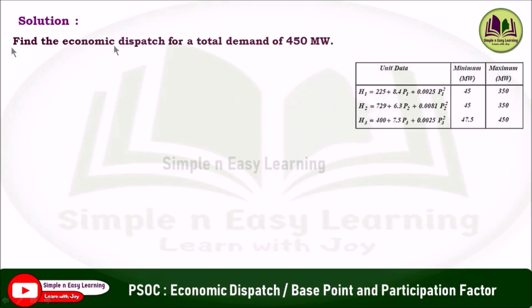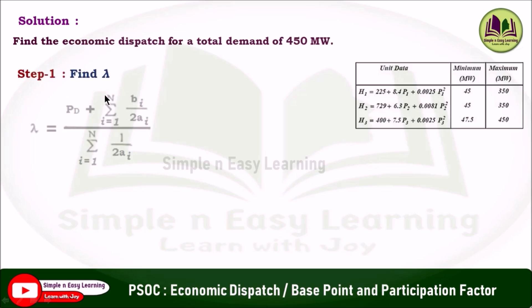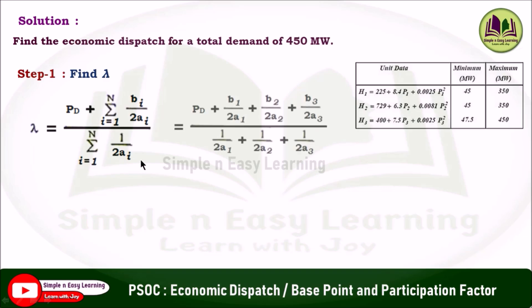Solution — Part 1: Find the economic dispatch for a total demand of 450 megawatt. Step 1: Find lambda using the formula: P_d plus summation (i=1 to n) of b_i / 2a_i, divided by summation (i=1 to n) of 1 / 2a_i. Substituting n = 3, the formula becomes P_d plus b1/2a1 plus b2/2a2 plus b3/2a3, divided by 1/2a1 plus 1/2a2 plus 1/2a3.